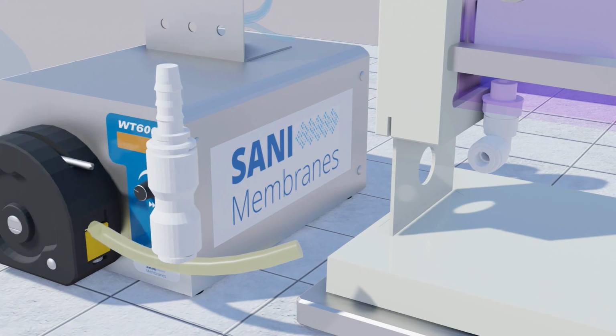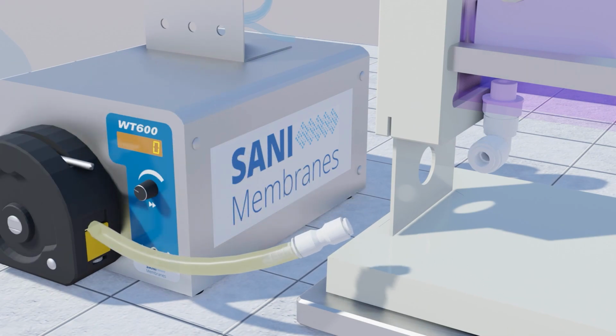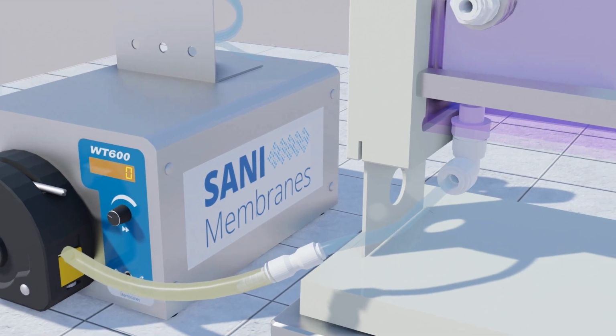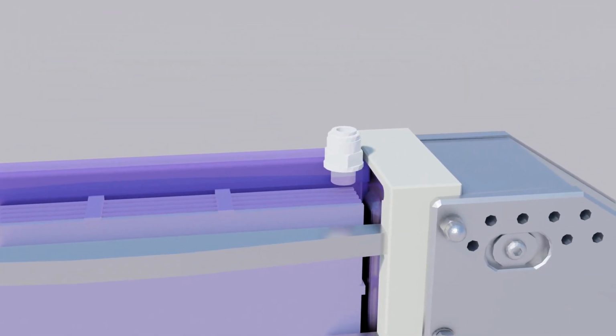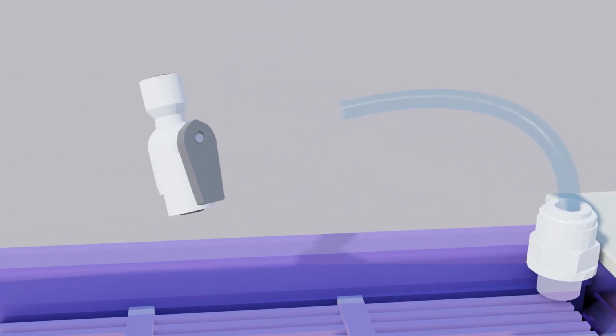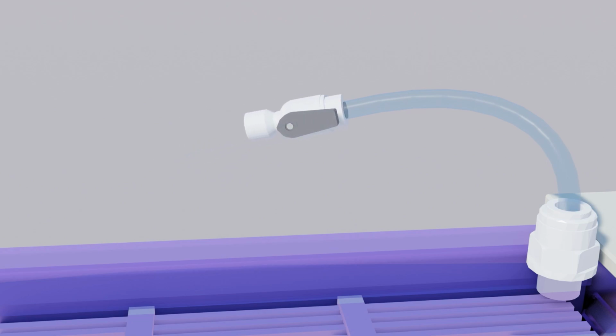Use the hose barb adapter to connect the pump tubing with the 8mm tubing and connect it to one of the media inlet ports. Diagonally opposite of the used inlet port, connect the 8mm tubing to the outlet and fit a regulation valve. Attach the 8mm tubing to the other end of the regulation valve and lead it into the feed vial or retentate vial, depending on your application.